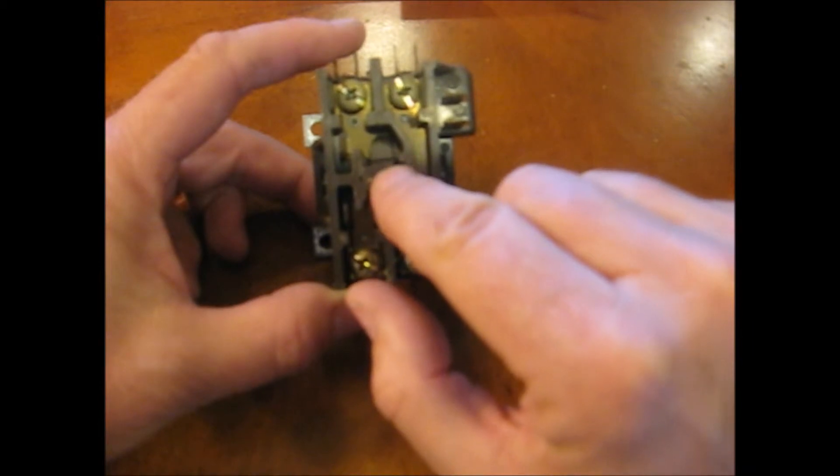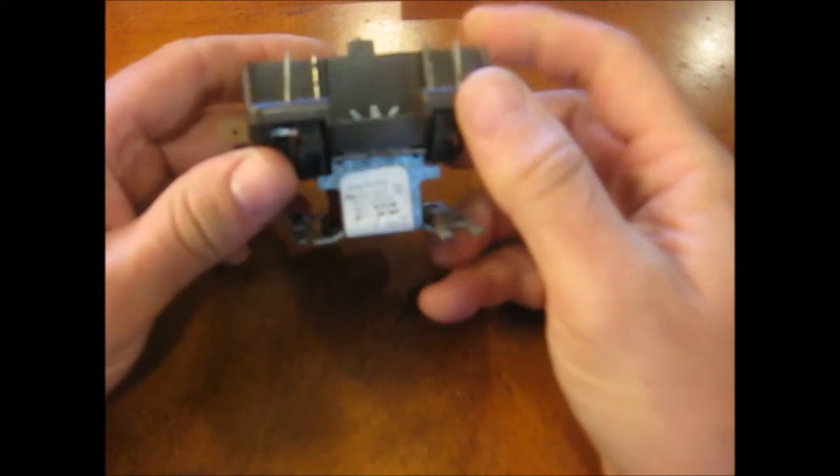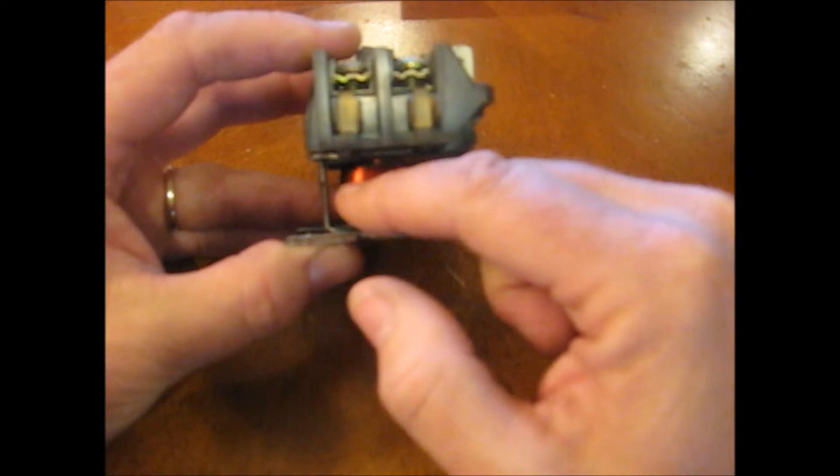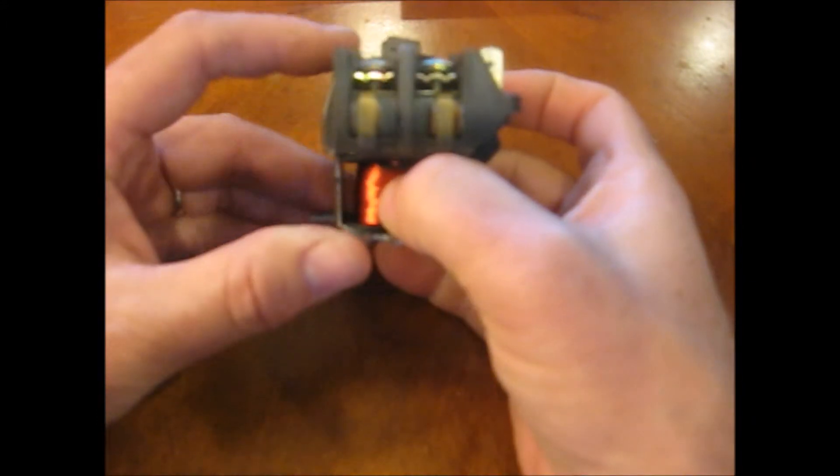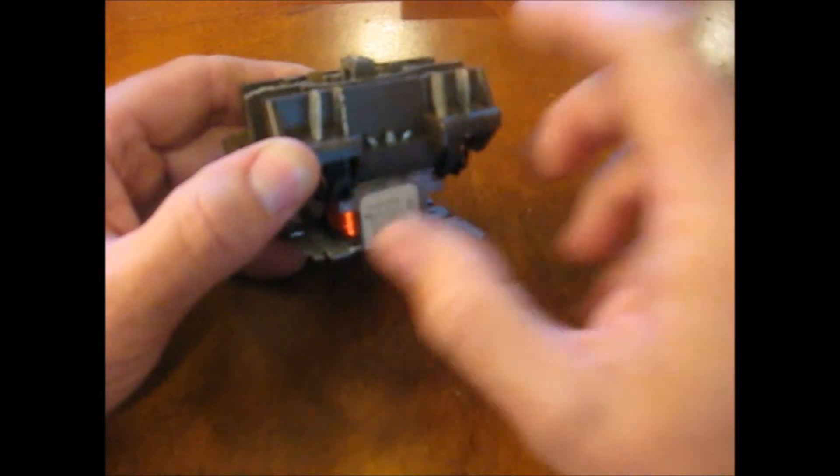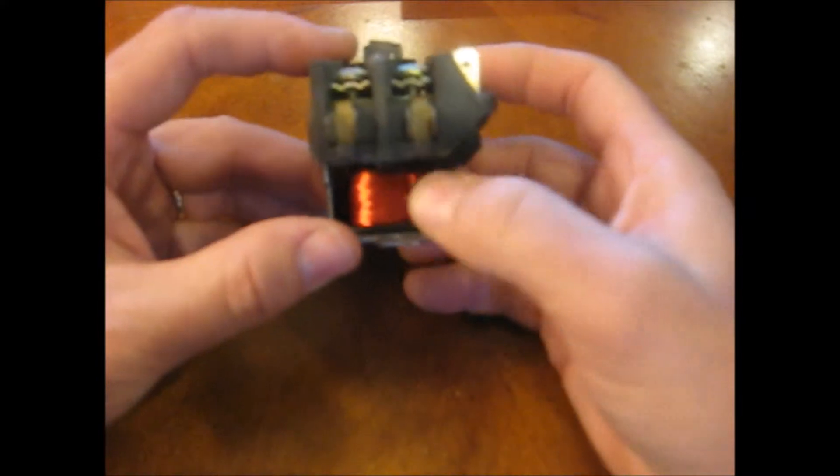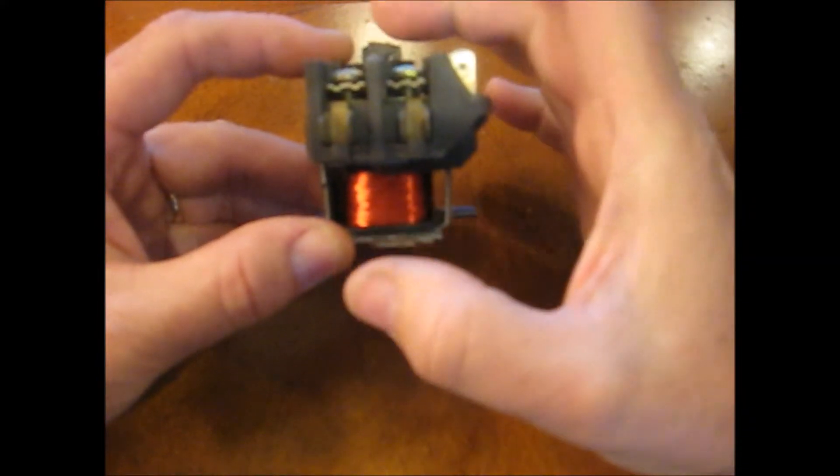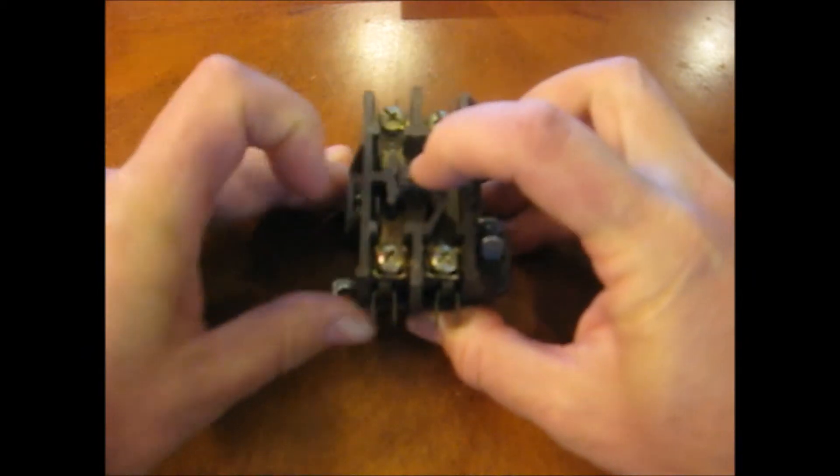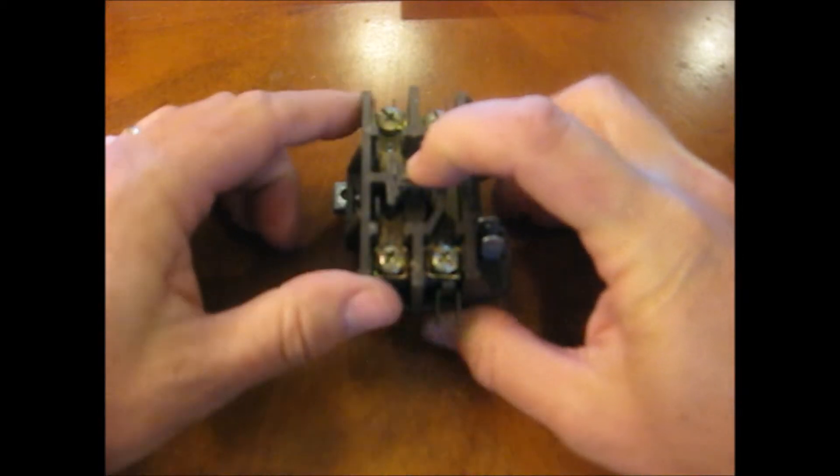The switch which is on a spring is controlled by a magnet. The magnet is an electromagnet and it is energized by this coil down here which runs on low voltage. The low voltage connections are here. So when this is energized it creates a magnetic field and pulls the switch down, connecting the line side to the load side of the contactor.